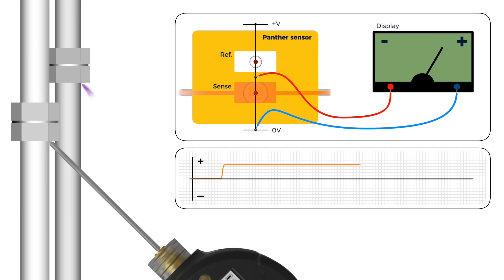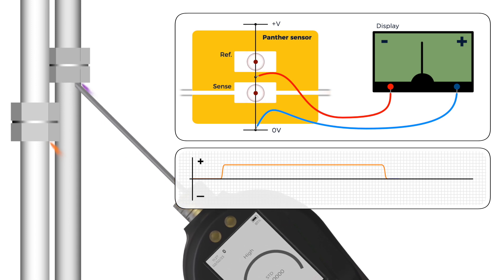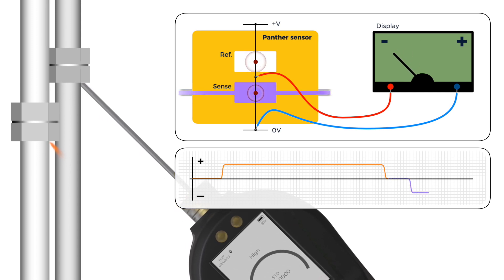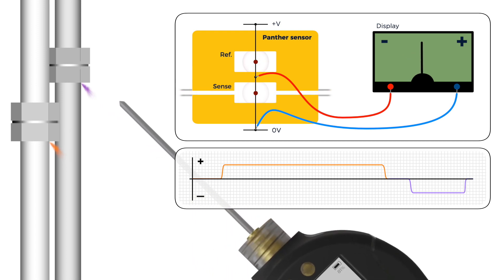This means the sensor can experience a negative or positive response depending on the gas. That said, to avoid confusion, the default setting on the Panther displays all readings as positive.